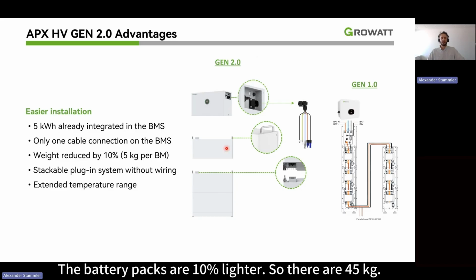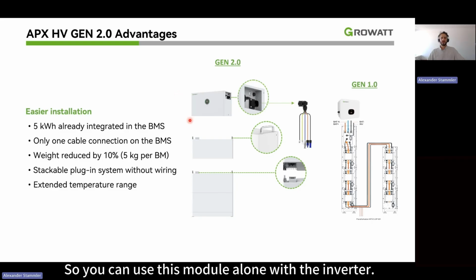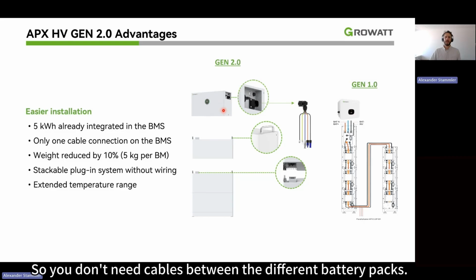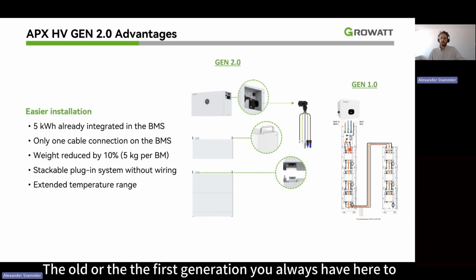The second generation is not so different. The big difference is, one, the battery packs are 10% lighter, so they're 45 kilos. They have some handles to carry. The BMS also is included with 5 kilowatt hours of battery storage capacity, so you can use this module alone with the inverter. You don't need to buy one BMS plus one battery. The communication goes all with one integrated cable, and it's stackable without cabling. So you don't need cables between the different battery packs. In the first generation, you always have to connect with cables between the BMS and each of the battery packs.